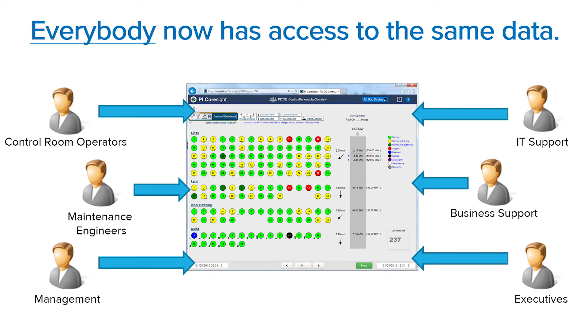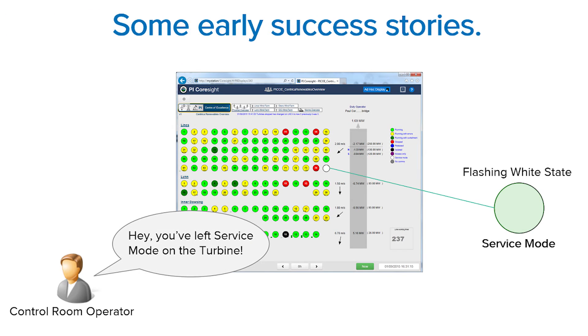When the operator went through that process and logged the return of the turbine back to him, rather than returning to a green PI — all running, everything's fine — it wasn't. It was flashing white, indicating a combination of statuses: basically saying it was left in local control and was not generating. That wouldn't have been immediately obvious, and it could potentially have been some time before the operator noticed, by which time the crew would be back on the vessel travelling home and you've lost the night's generation on that turbine.